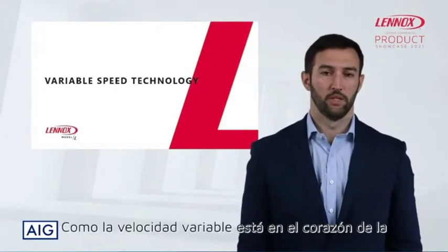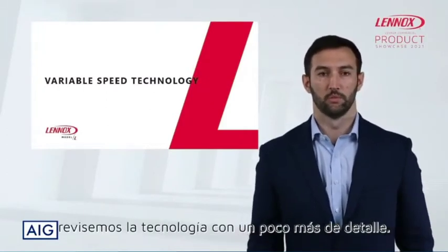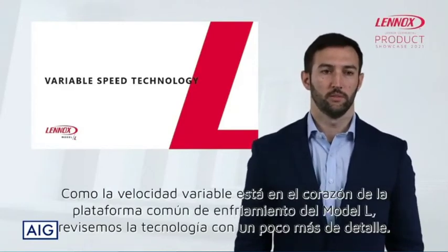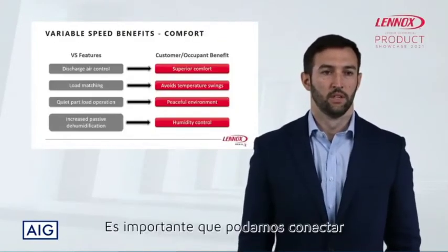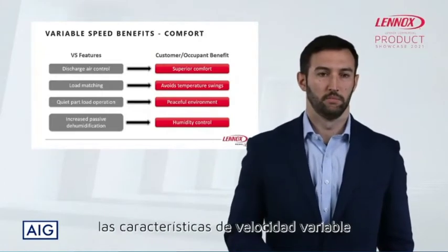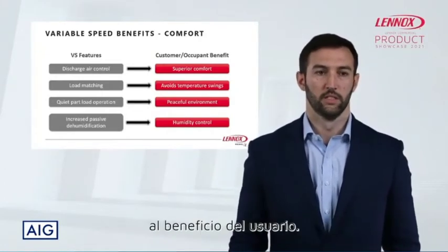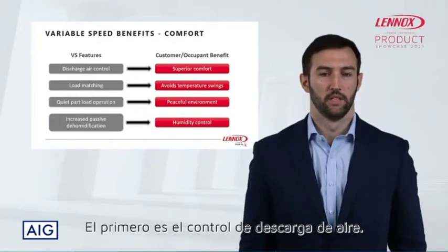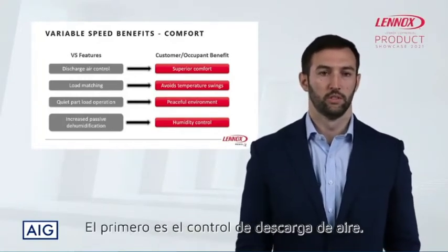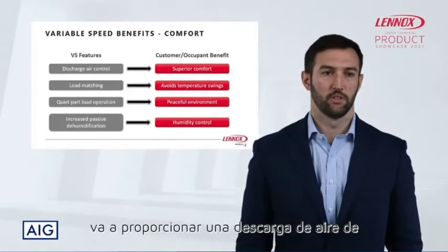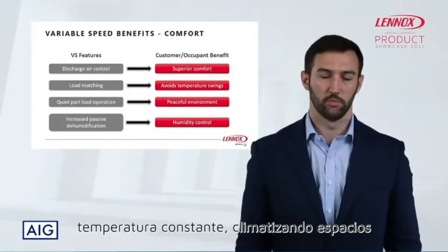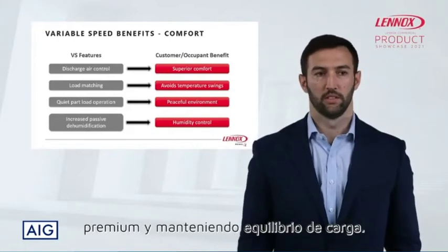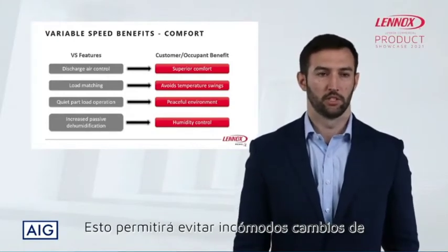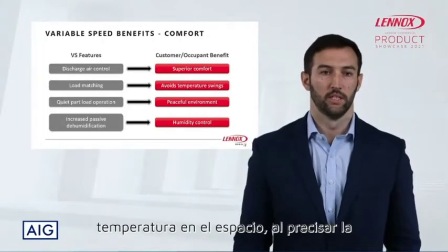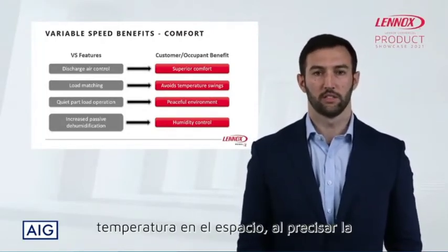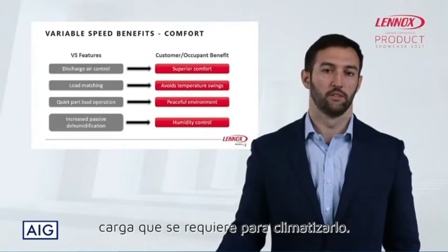And so since variable speed is at the heart of the Model L comfort cooling platform, let's review the technology in a little more detail. So it's important that we can connect the benefits and the features of variable speed to the end user or customer benefit. And so the first is going to be discharge air control. And Model L with the variable speed compressor is going to provide a constant discharge air temperature for premium space comfort. And then load matching. So this is going to allow us to avoid uncomfortable temperature swings in the space by matching the load that is required for that space.